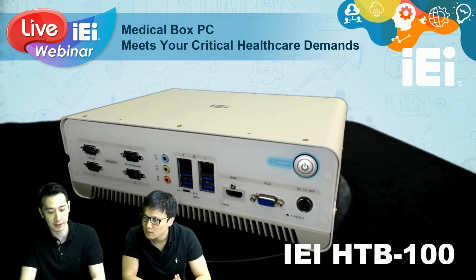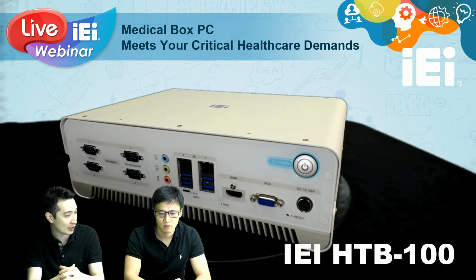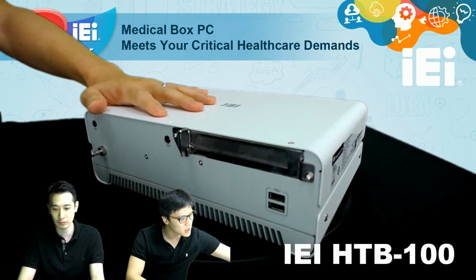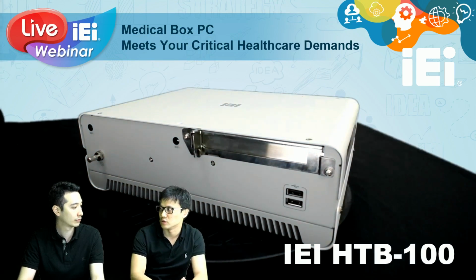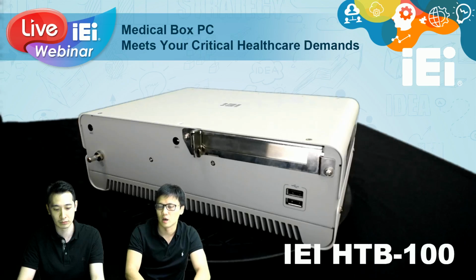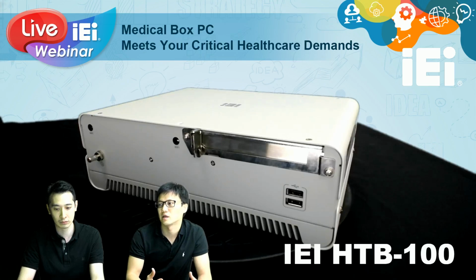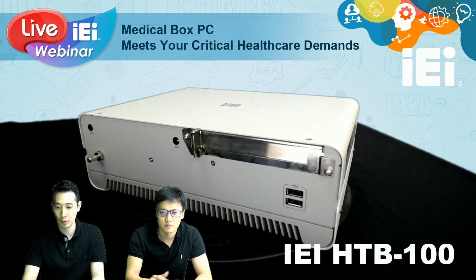Okay, the third question we have here. Besides the capture card, are there any other cards we can use with this system? Like I just mentioned, this system supports a PCIe x16 expansion slot, so any card that can fit in this dimension can be used in this system, but we have to think about the thermal issue and the application. Usually in the hospital or in any medical situation, we use something like a capture card for image inspection.